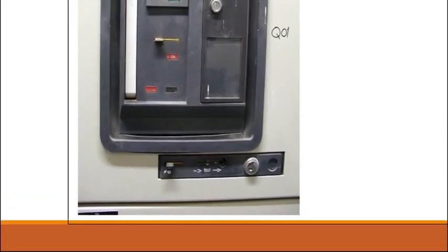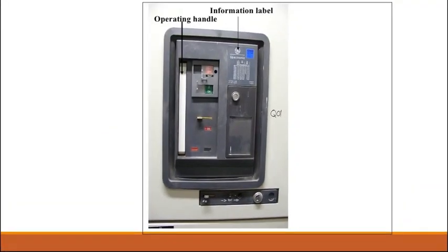And here, this one gives the information on the position of the breaker, whether it is in test position or in service position. Here we have also provided padlocking applications. The purpose of padlocking is, for example, if I keep the breaker in test position, only an authorized person can do the operations. For HSE precautions, we have given this padlock system in new breakers.